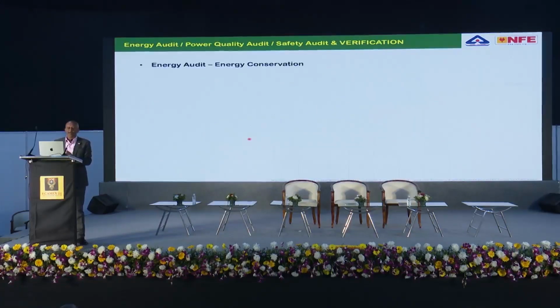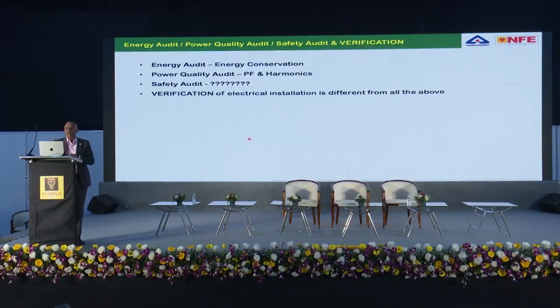Let me go back. When we talk about the last part, NEC talks about design, selection, erection, verification. The last part is verification. People always say energy audit. But with respect to electricity, there are different kinds of audits. Energy audit, which is the primary subject, is about conservation: using devices or saving energy is the main target. Power quality has its own requirement. Safety audits are also carried out in several installations, but so far this fault loop impedance test or the other tests were not common.